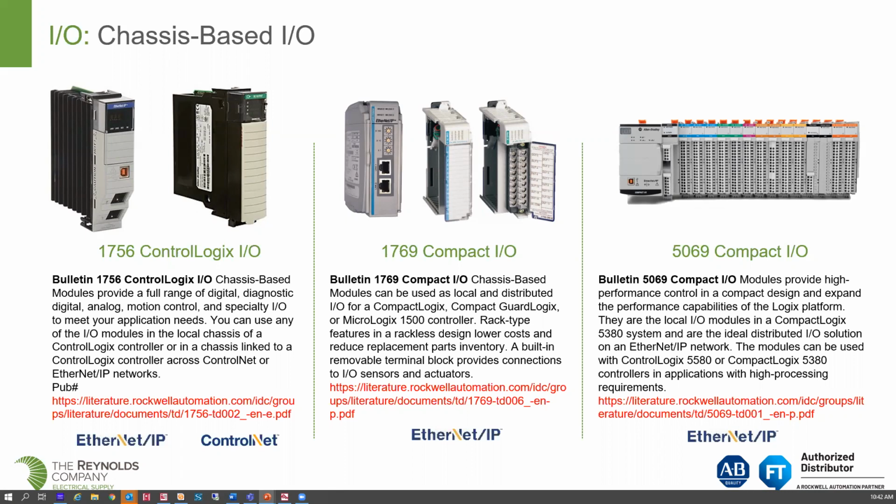Currently, we still support Ethernet, and ControlNet as the comms for these racks, but typically we see people using this in a lot of small process systems where they don't want to use the same form factor of IO throughout the facility. That's why remove and insert under power is very important to them. These generally come in IO increments of 8 to 16 points, but we can do 32 points of discrete with them.